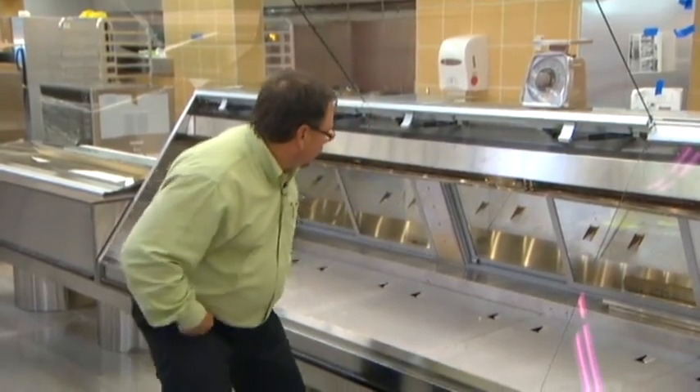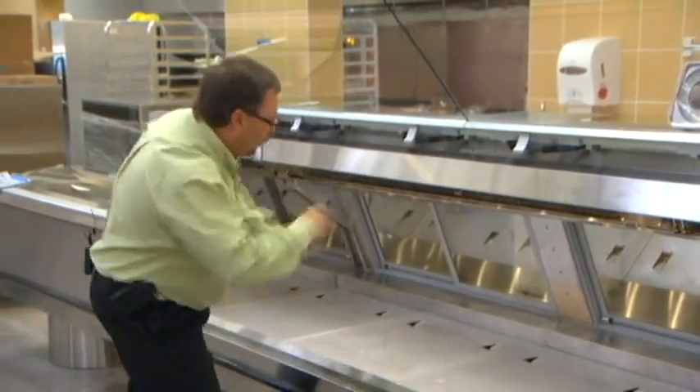With the gravity coil sitting up here on top, one of the things you're going to first notice is the slope of the drain pan. When we look at the drain pan, there's a little bit of water sitting inside — that's perfectly normal. We don't mind seeing a few droplets because, as mentioned earlier, we have a wet coil. We want that coil wet and we want the humidity to be high. During defrost, a larger amount of water will come through.